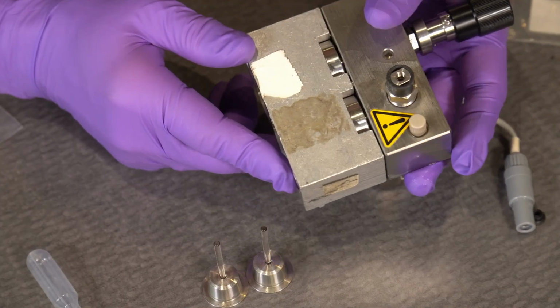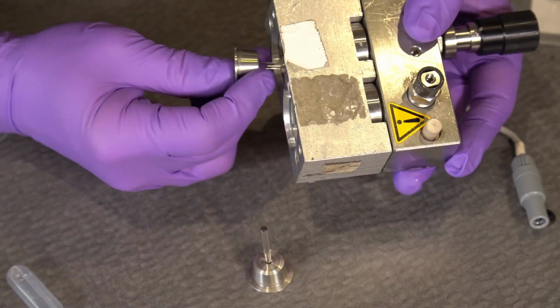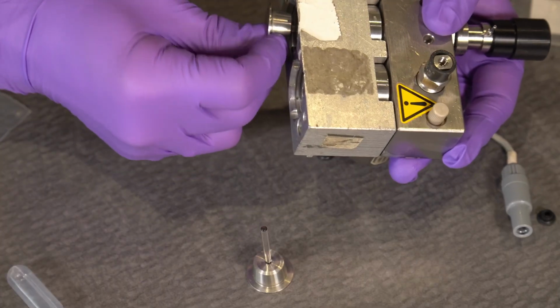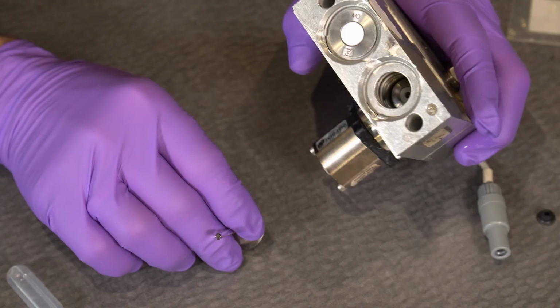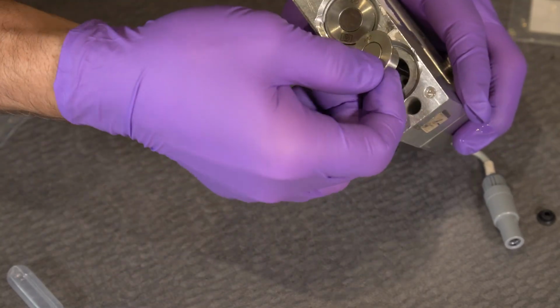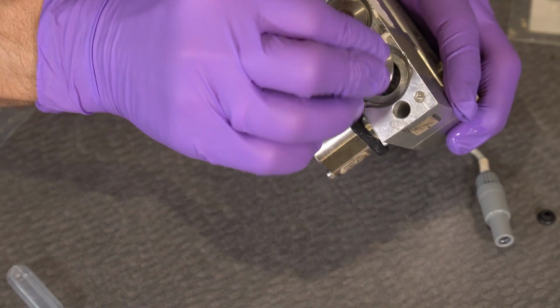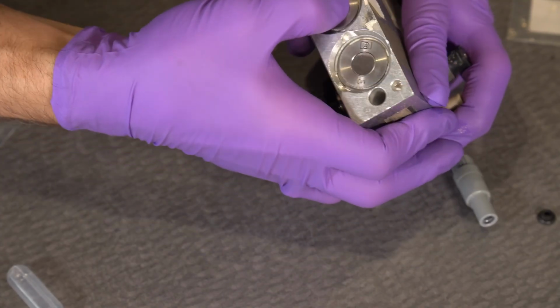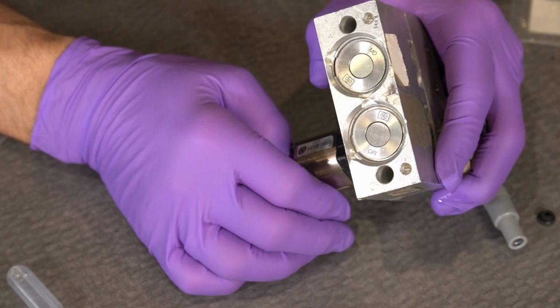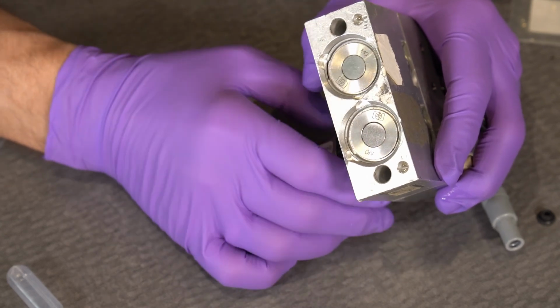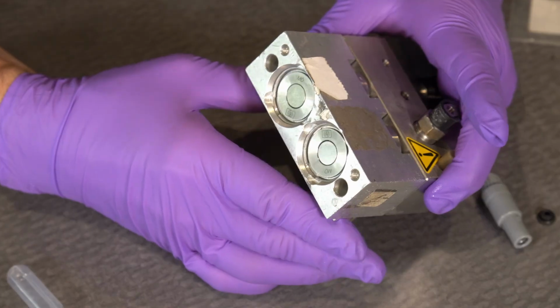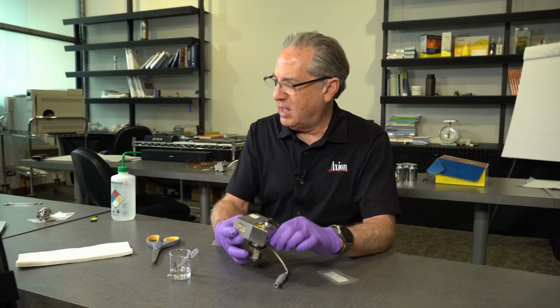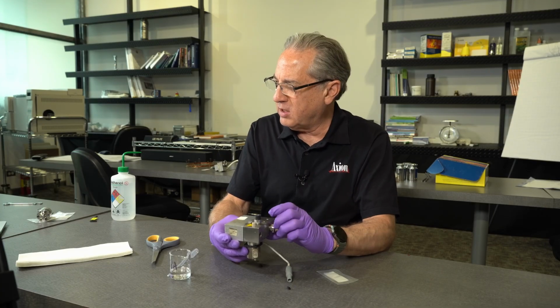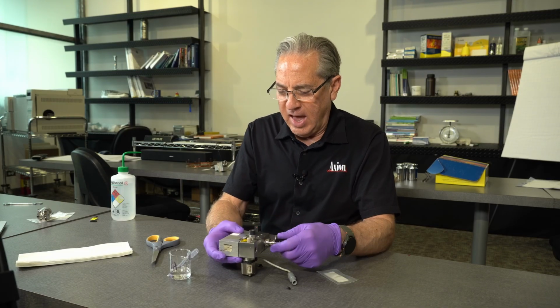And the last thing you do before you go back to the pump is take your pistons and stick the pistons into position. The reason I say we do this last is because the pistons are not really held in by anything. Sometimes there's a little bit of liquid cohesion that holds them in, but they will fall out. And I always joke that a piston will never break inside the HPLC. It'll only break if you drop it on the ground. So let's minimize the chance of dropping it. At this point, we have brand new pump seals. We're going to put this onto the HPLC instrument, and it's ready to go.